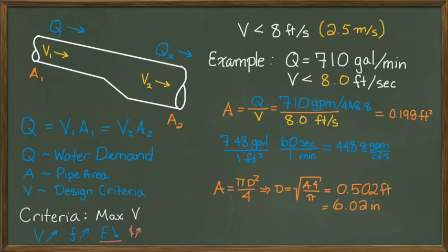Since there is no pipeline that is exactly 6.02 inches, we need to round up to the next standard diameter size, which is 8 inches. And that's how we use conservation of mass to size a pipeline when we are given a maximum velocity criteria.